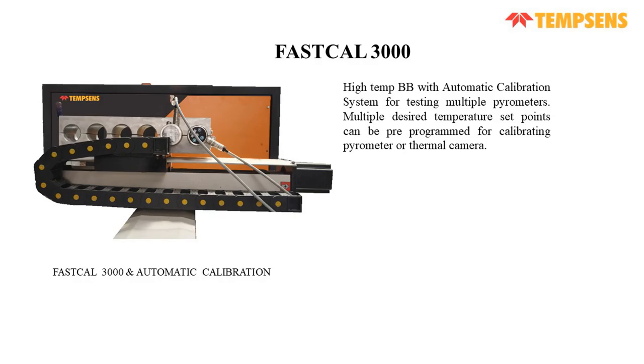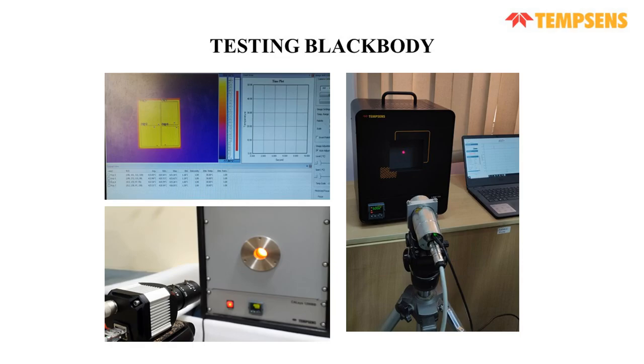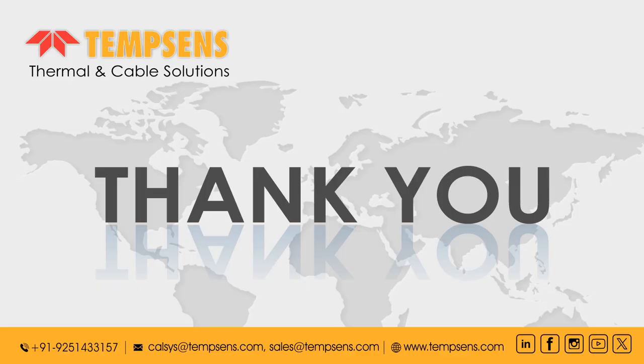It can incorporate an XY moving system in which pyrometers can be mounted, with a master, then test 1, test 2, test 3, depending on the requirement of the customer. Multiple desired temperature set points can be pre-programmed for calibrating pyrometers or thermal imagers. So this is how we test black bodies. Thank you.